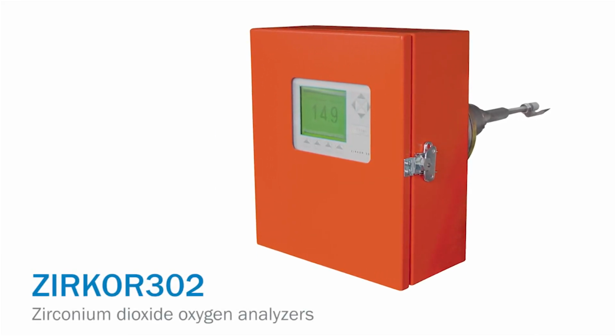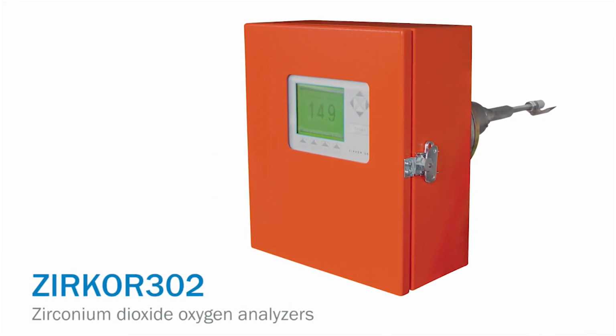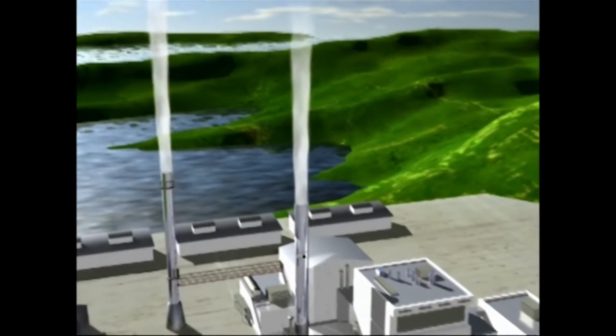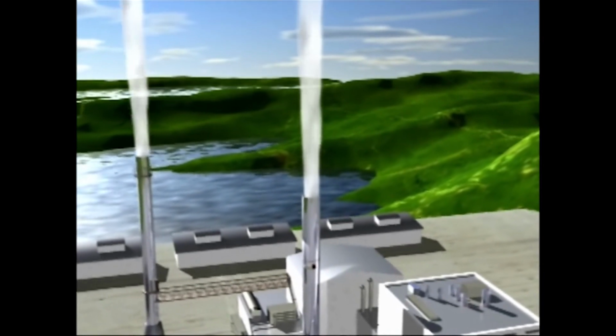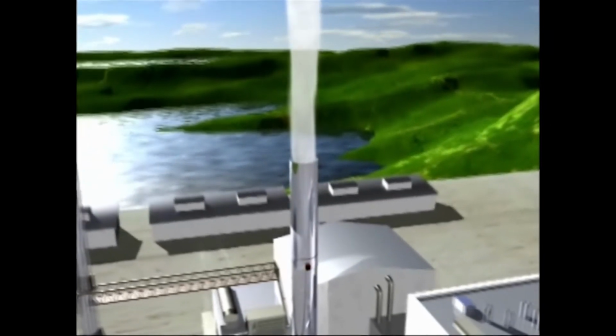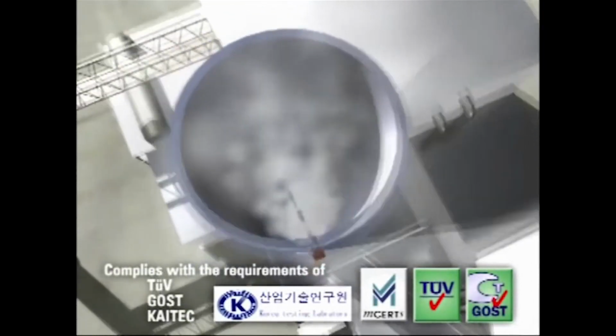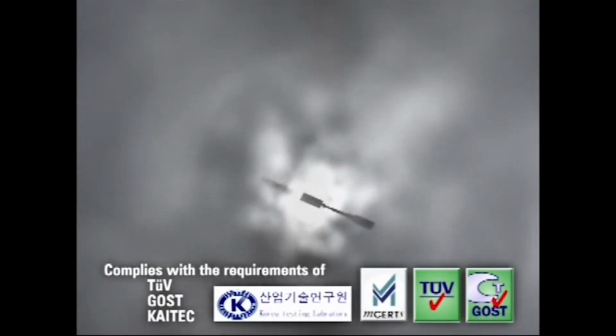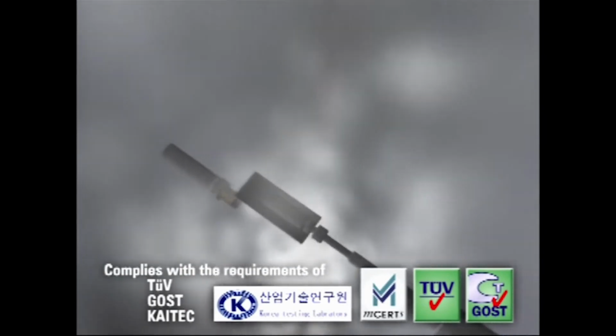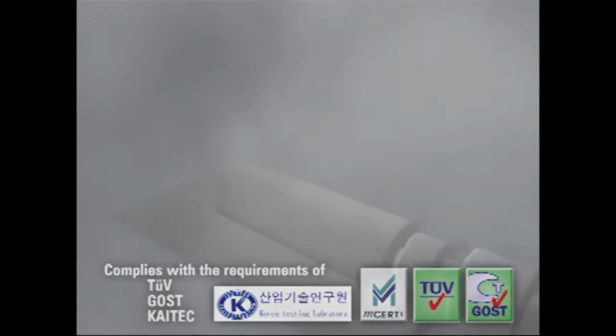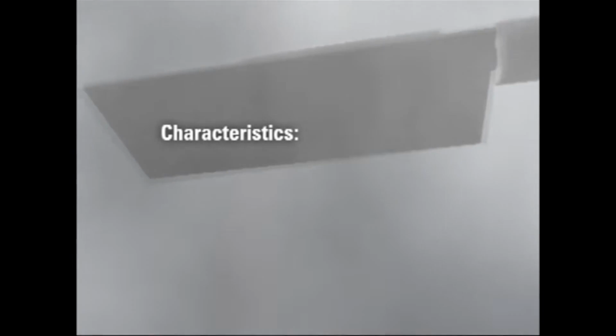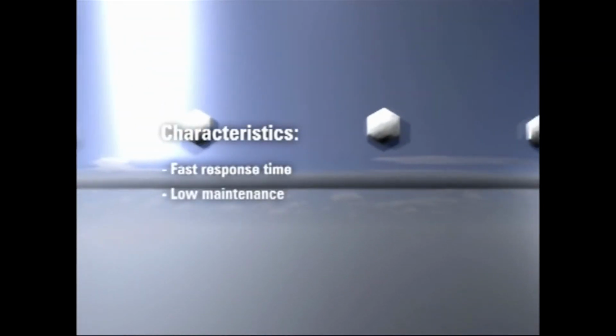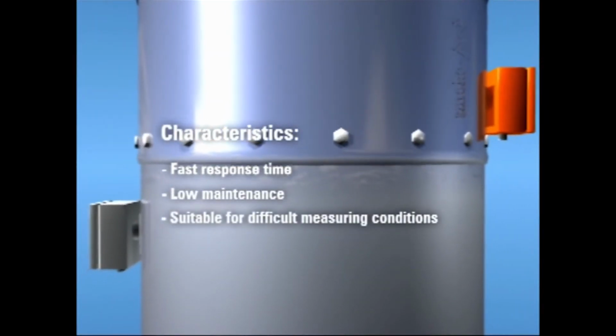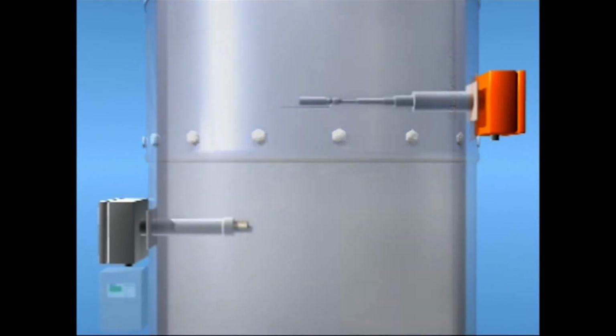ZIRKOR302, features of the zirconia current principle: linear measuring signal with fixed physical 0 point, fully automated calibration using ambient air, no additional test gases are required, auto-check function, minimal operating costs. These instruments are certified for a variety of national legal requirements regarding the measurement of oxygen in flue gas. Characteristics: fast response time, low maintenance, suitable for difficult measuring conditions.